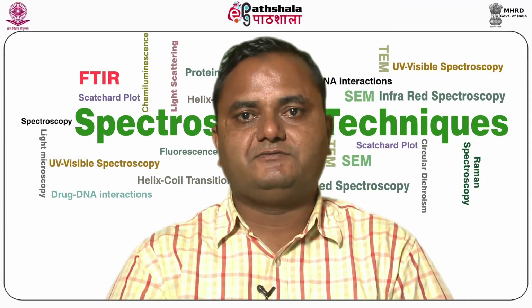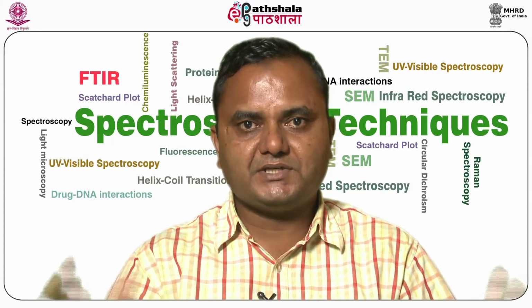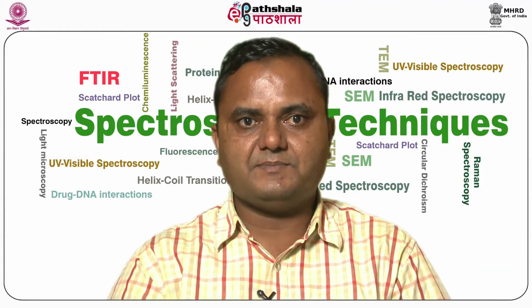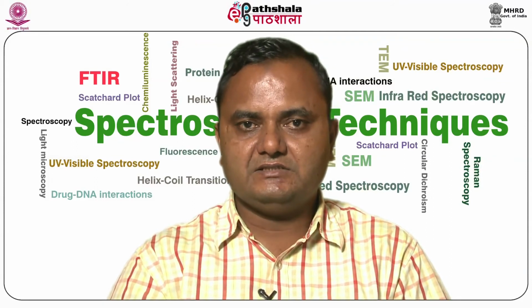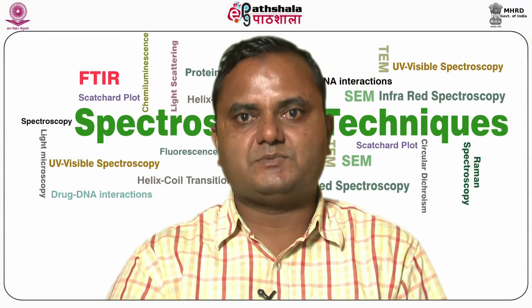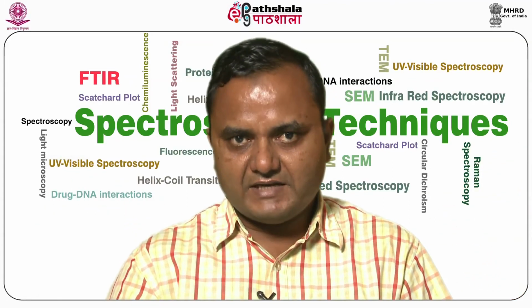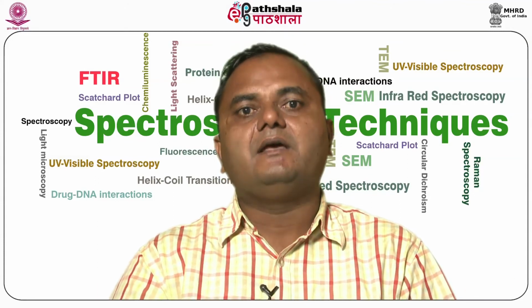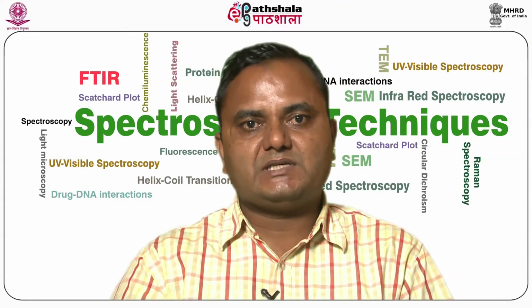The light from the source, an HCL, passes through the furnace and absorption during the atomization step is recorded over several seconds. This makes ET-AAS, electrothermal atomic absorption spectroscopy, more sensitive than flame atomic absorption spectroscopy for most elements.